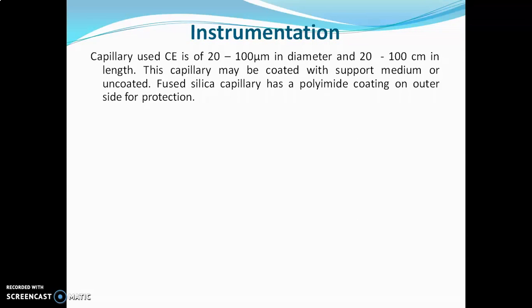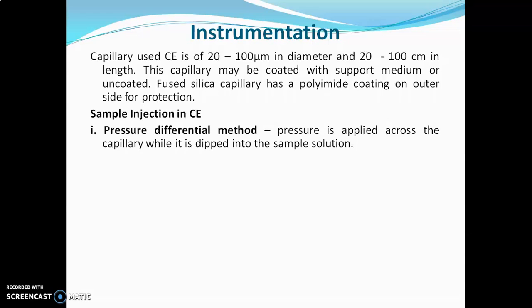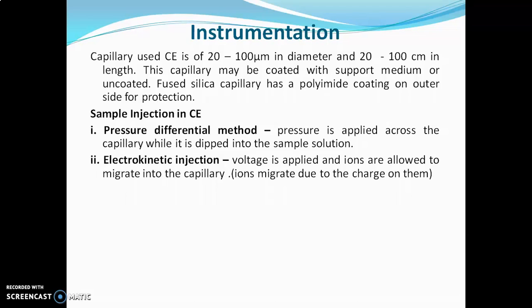Capillary used in capillary electrophoresis is 20 to 100 micrometers in diameter and 20 to 100 cm in length. The capillary may be coated with support medium or it may be uncoated, and there are types of capillary electrophoresis depending on this. The fused silica capillary has polyimide coating on the outer side for its protection. There are two types of sample injection: first is the pressure differential method, where pressure is applied across the capillary while it is dipped into sample solution; and second is electro-kinetic injection, where voltage is applied and ions are allowed to migrate into the capillary.